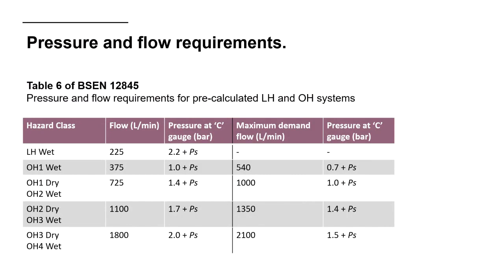0.098 bar pressure loss per metre. So in basic terms, 10 metres is 1 bar. Every 10 metres you go up, you need basically an extra bar of pressure on the town main. And then we have our maximum demand flow, 1350 litres a minute at 1.4 bar plus the static pressure. So again, we've got 2 points on our curve that our town main needs to achieve. And as I say, if we are looking at the boosted statement, then we need to add 20% to the flow characteristics. So this table is a good starting point in terms of whether our town main is sufficient. We can do a test, compare it to these figures, and tick that box.